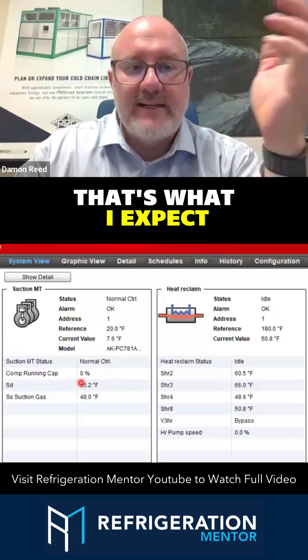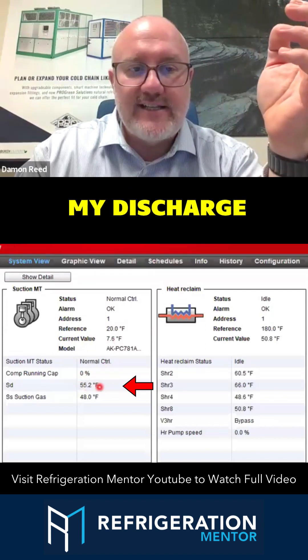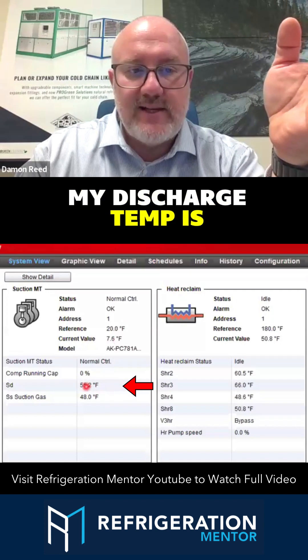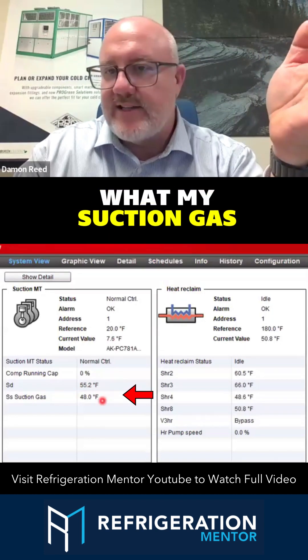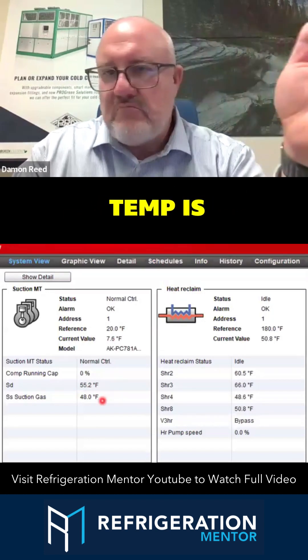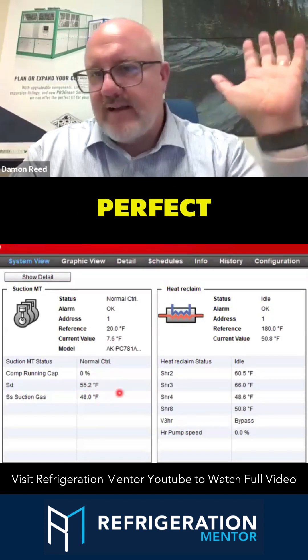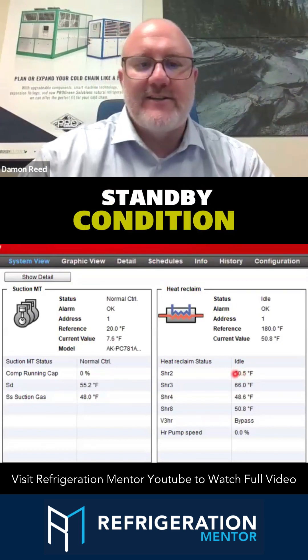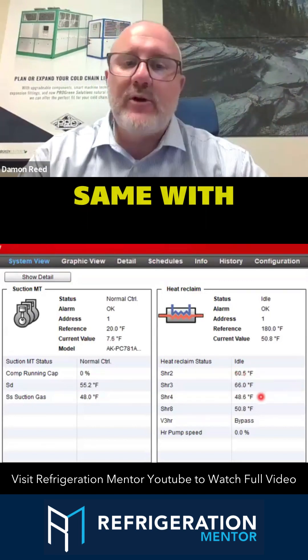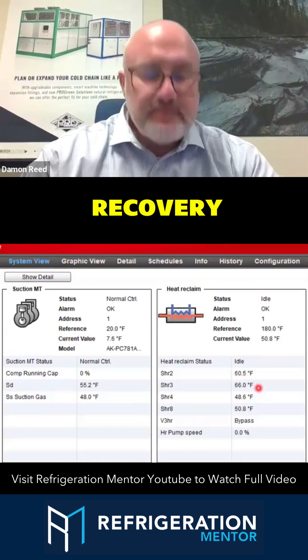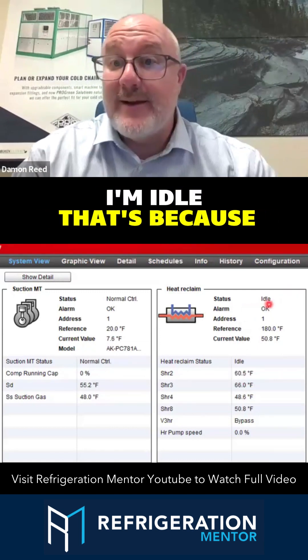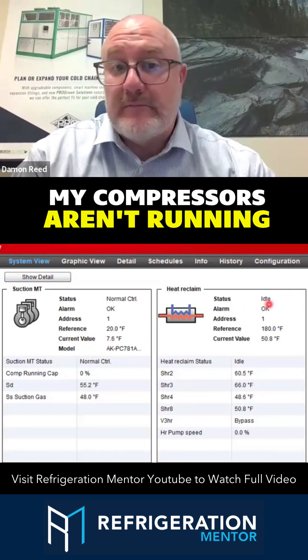I can see what my discharge temp is and what my suction gas temp is. That compressor is in standby condition — it's just holding. Same with the heat recovery. I can see that view and it's idle, because my compressors aren't running.